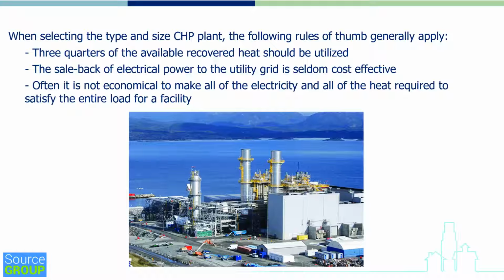The sale back of electric power to the utility grid, that is the local distribution company, generally is not cost effective. They will pay something, but it's usually not enough to cover the cost of generating the electricity. Often, it's not economic to make all of the electricity or all of the heat required to satisfy the entire load of the facility. There are strategies such as electric load following, thermal load following, base load following, base thermal load following. There are different scenarios used operationally to blend the production of electricity and heat in the most cost-effective way.